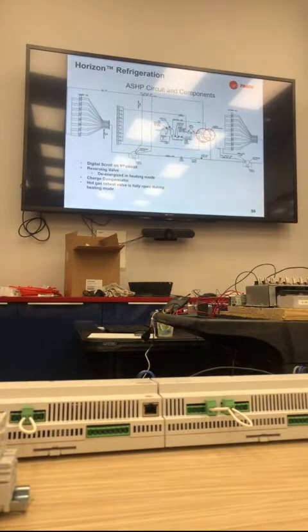Then the heat pumps themselves are pretty much the same thing. Our older air source heat pump units that I really wanted to look at real quick had to have more refrigerant in heating mode than we did in cooling mode. Cooling mode required less refrigerant, so we had to install a charge compensator. Has anybody heard of a charge compensator for heat pumps?